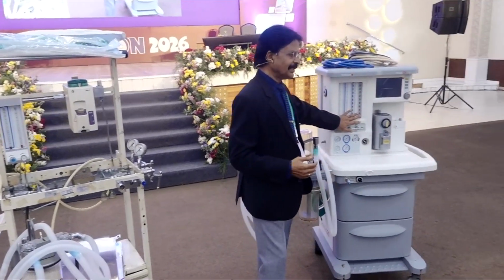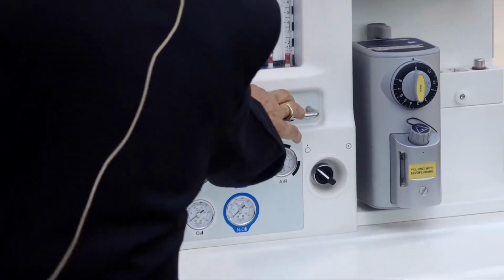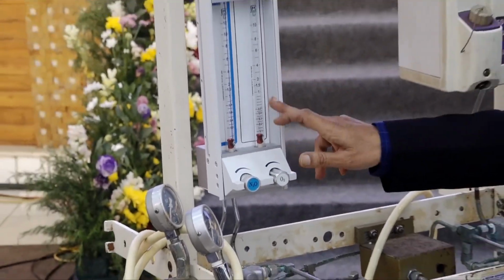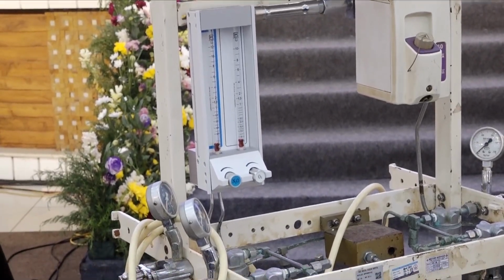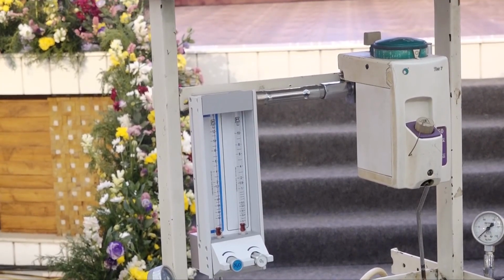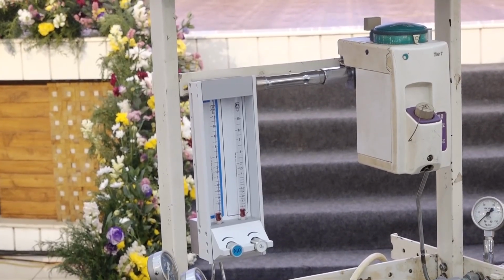Now coming to the flow meter assembly, now we have the flow meters, the flow control knobs. These are the flow control knobs you can see here. So in the older machine, if you just see, one tube for oxygen, one tube for nitrous. The problem with a single tube for each gas is that it is very difficult to go for low flow anesthesia accurately. Suppose I want to give just 250 ml of oxygen, metabolic flow, as far as low flow anesthesia is concerned. I will not be able to provide that with these machines.